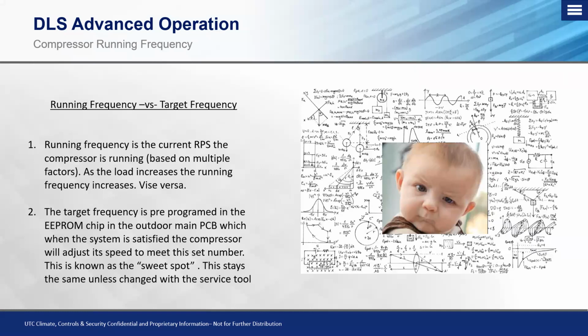So diving into the running frequency. The running frequency is the current RPS, or revolutions per second, often referred to as well as hertz or frequency, that the compressor is running. This is based on multiple factors. As the load increases on the system, the running frequency, or the speed of the compressor, is going to increase as well. And opposite of that, as we have a decrease in load, the running frequency is also going to decrease.